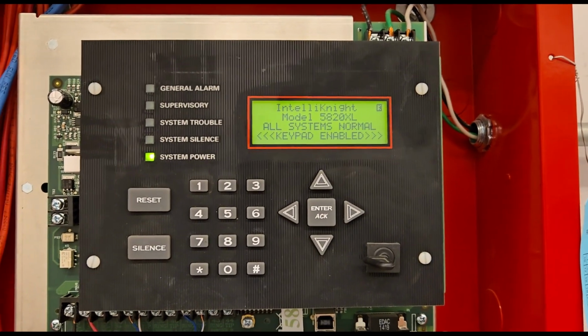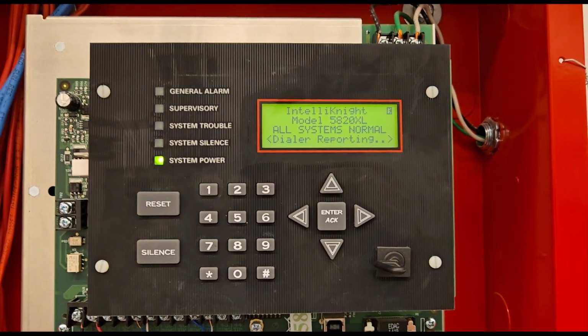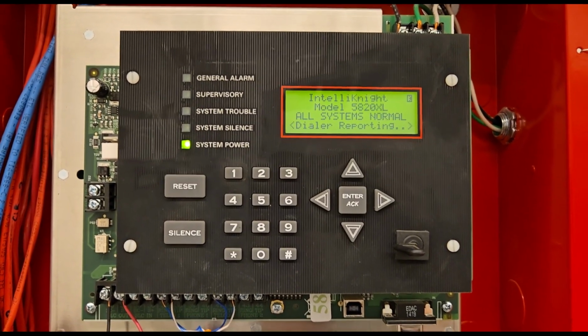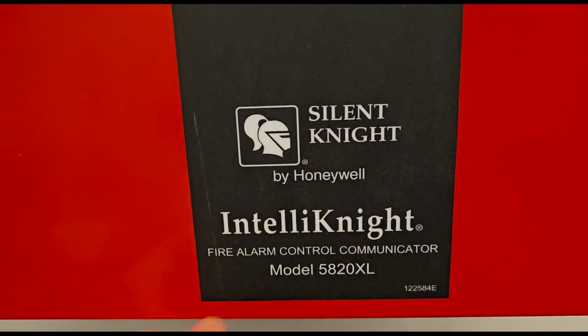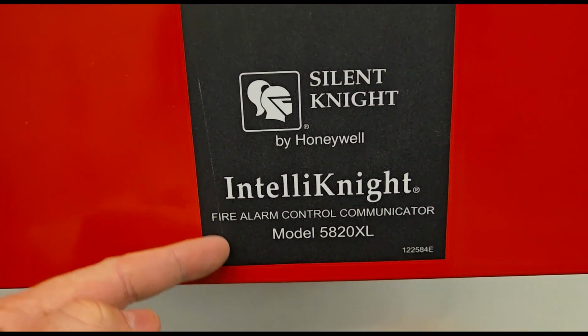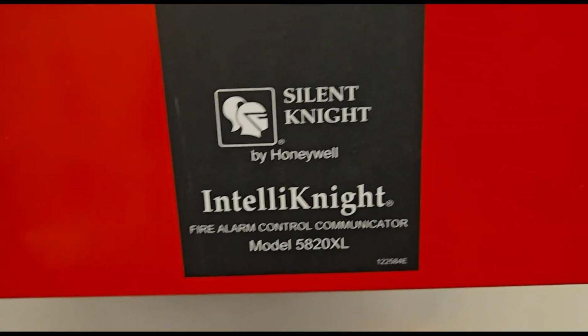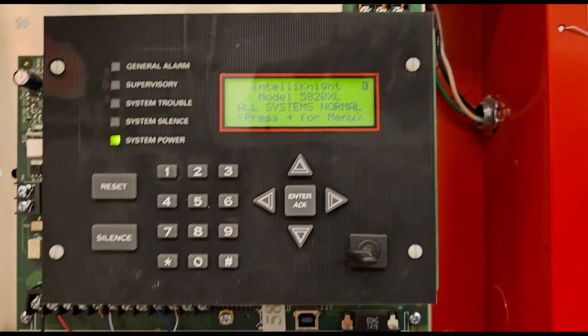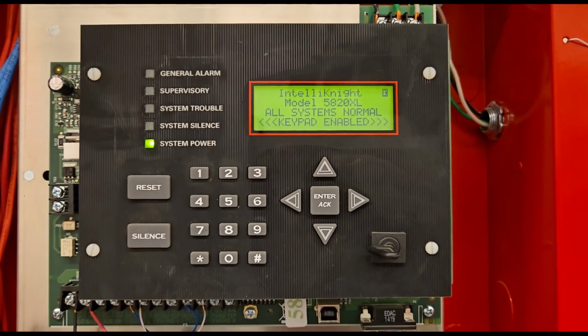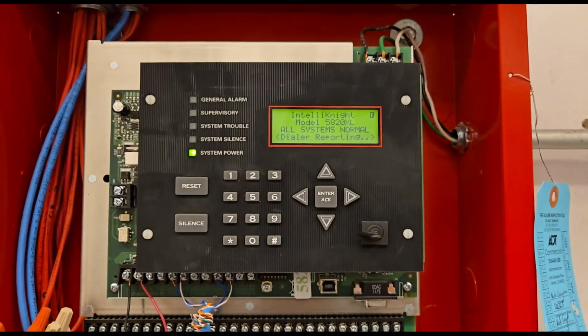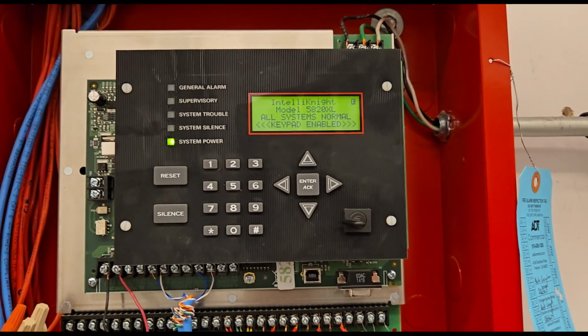In this video, I'm going to show you how to do the AC breaker disconnect test for the fire alarm panel. This is a Silent Knight by Honeywell. It's an IntelliKnight 5820XL. So this is the panel make and model. We want to do our disconnect test to verify that the breaker is correctly identified and functions.